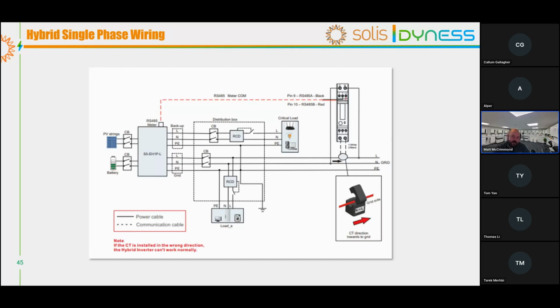What we would always advise is that if they were putting critical loads on it, they would maybe suggest putting a transfer switch between the grid and the loads, so that only in the event that the inverter fails and the grid fails, you don't lose the critical load. Because ultimately what you wouldn't want to happen is, in the event of a power cut, the inverter failing, or maintenance needing done on the inverter, for example, you have the AC grid there, but you can't supply your loads because it's connected to the output of the inverter. So always consider that when you're doing that.